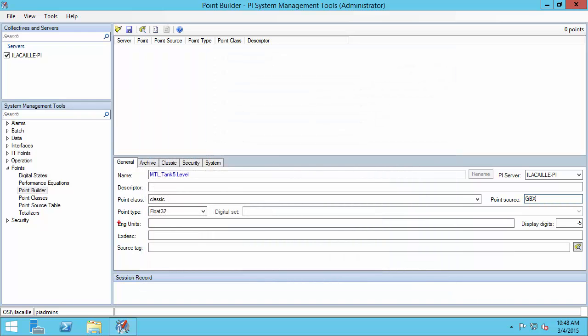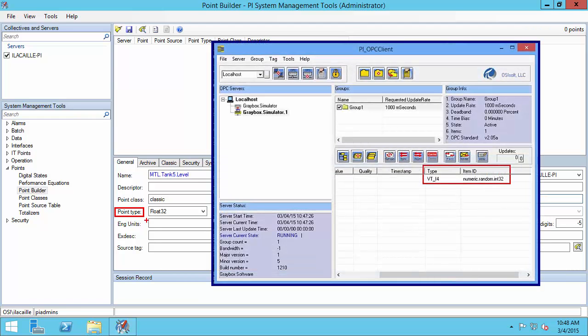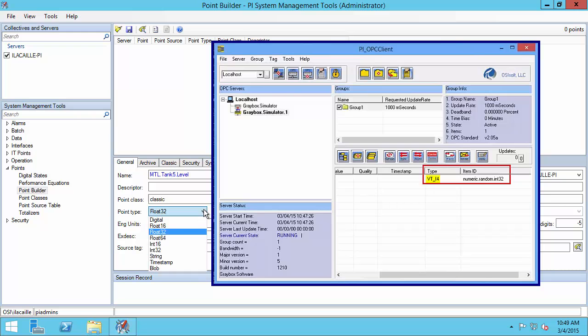Finally, I need to make sure that the point type is compatible with the data type on the OPC server. The PI Interface for OPC DA User Guide has a section that explains specifically which OPC server data types are compatible with which PI Data Archive data types. My data type is VT_I4, which means a 4-byte integer, and this corresponds to Int32 on the PI Data Archive.